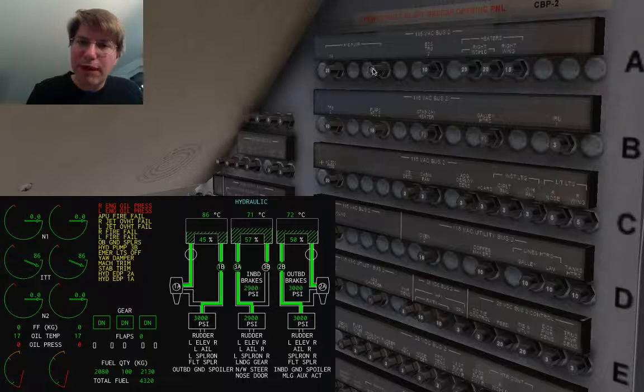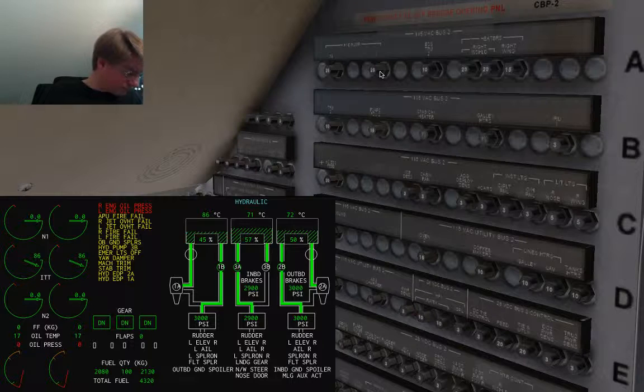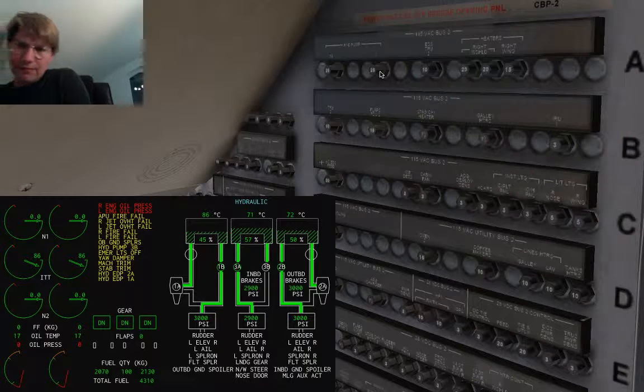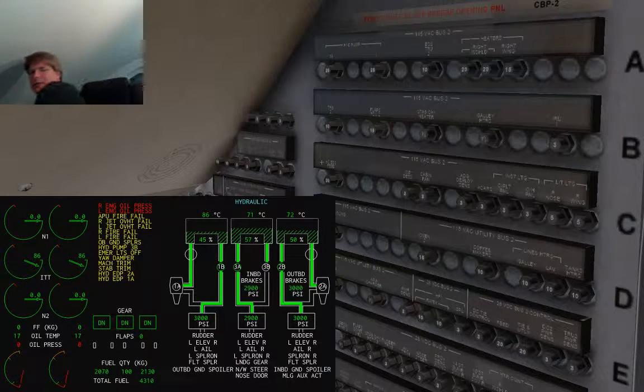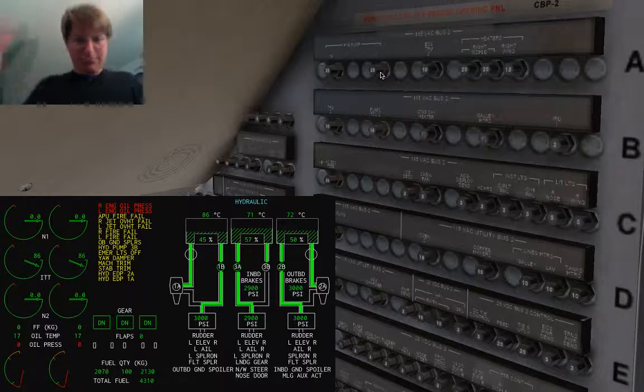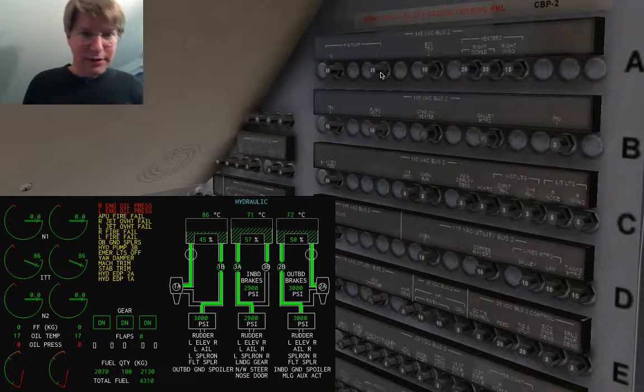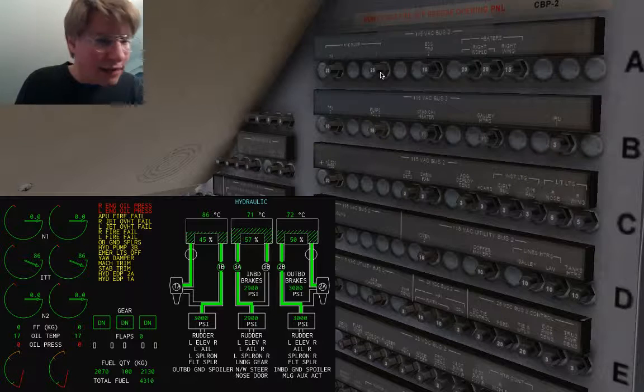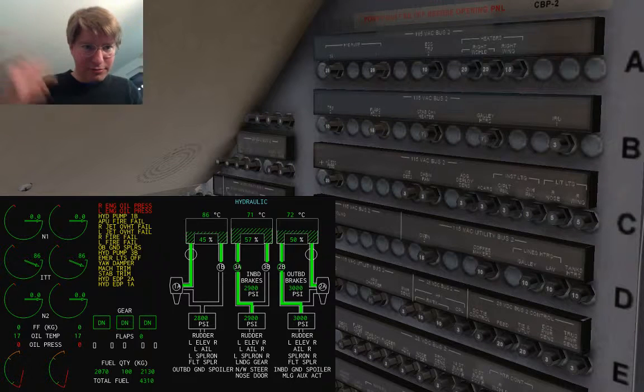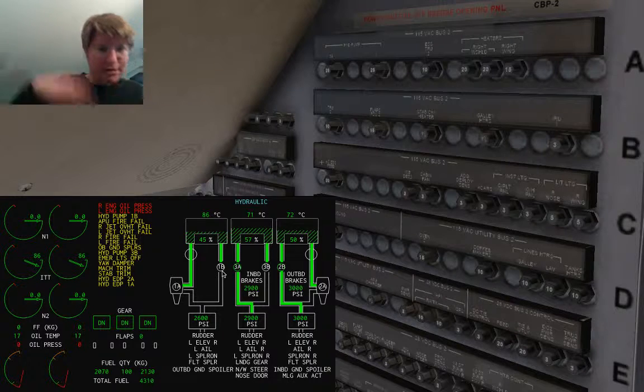Yeah, hydraulic pump 1 — that's this one. It's a 25 amp circuit breaker. So let's kill that, 2A5. Again, in the actual model you could just click it and the circuit breaker would come out, as long as Javier hasn't animated it — I just use the REST API again. So 2A5 is the one to kill. 2A5, bam, circuit breaker pulled. And as you can see here, the pump has dropped offline.